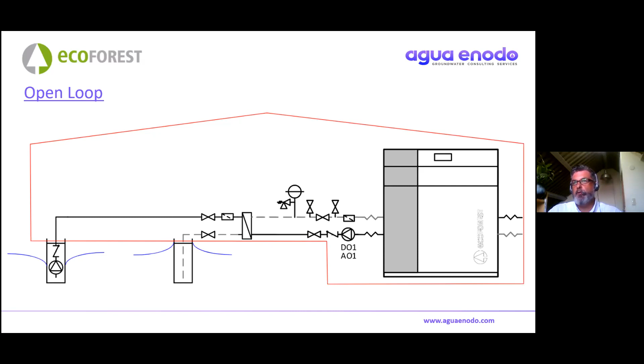You can see that in this case, this is a pump and dump system. We have the abstraction well on the left-hand side, which draws water to the well, so you can see we have something called a cone of depression around that well. The blue lines dovetailing down to that well indicate that we drop the water level in one well in order to take that water out. Then you can see the plate heat exchanger somewhere in the basement that isolates the heat pump from the water.